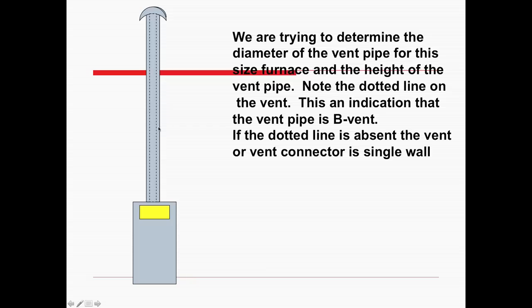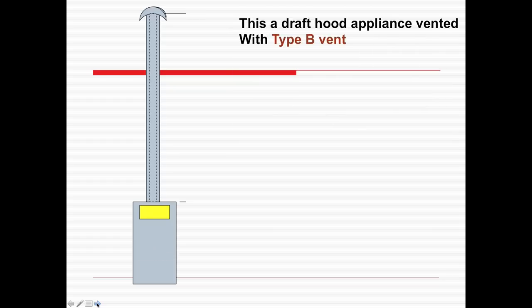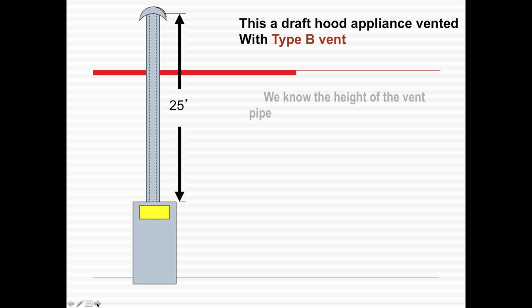We're going to determine the diameter of the vent pipe for this furnace. These dots indicate this is Type B double wall vent. If there is no double wall vent, it'll just be a single line. It's a draft hood appliance. It's 100,000 BTUs, Type B vent. The vent height is measured from the very top of the furnace where the connection to the vent is, to the top of the vent termination — 25 feet.